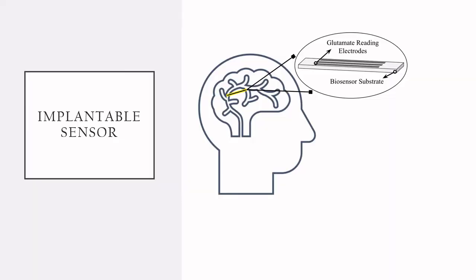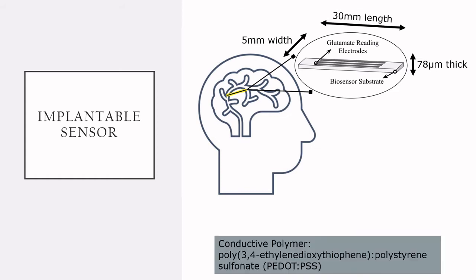The sensor is implanted in the brain and manufactured with a Clark platinum electrode that utilizes glutamate oxidase to indirectly measure glutamate levels by its breakdown products. The dimensions are 30 by 5 millimeters and 78 micrometers thick. The sensor is 3D printed using a sterilizable and biocompatible conductive polymer called PEDOT:PSS, which is flexible and puts minimal mechanical strain on the tissue.